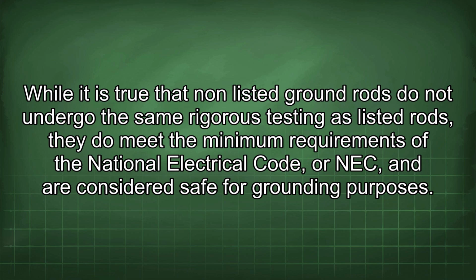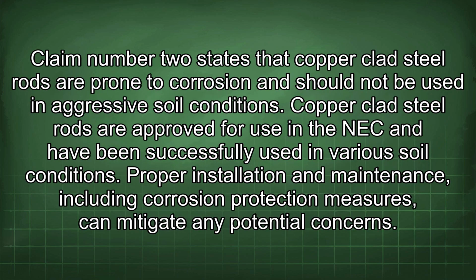they do meet the minimum requirements of the National Electrical Code, or NEC, and are considered safe for grounding purposes. Claim number 2 states that copper-clad steel rods are prone to corrosion and should not be used in aggressive soil conditions. Copper-clad steel rods are approved for use in the NEC and have been successfully used in various soil conditions. Proper installation and maintenance, including corrosion protection measures, can mitigate any potential concerns.